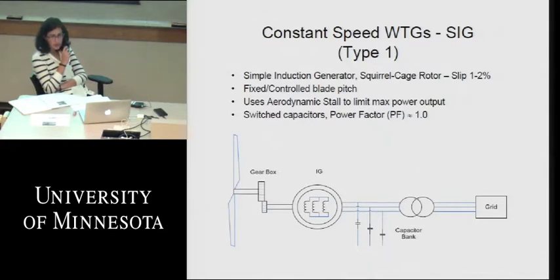And these banks are multi-switched because there is a certain requirement to magnetize the core of the generator, but as you keep increasing the power output, it tends to draw more and more VARs into the generator. And as such, we step in increasing amounts of capacitance to offset that as power goes up and down out of the generator. Okay, next slide.